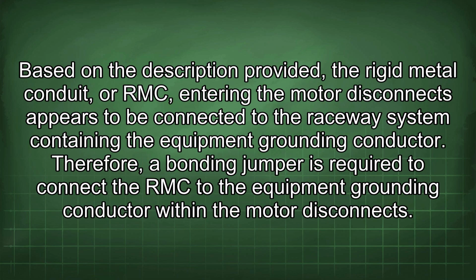Based on the description provided, the rigid metal conduit, or RMC, entering the motor disconnects appears to be connected to the raceway system containing the equipment grounding conductor. Therefore, a bonding jumper is required to connect the RMC to the equipment grounding conductor within the motor disconnects.